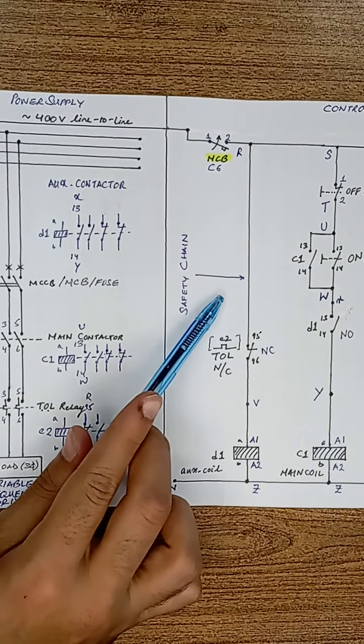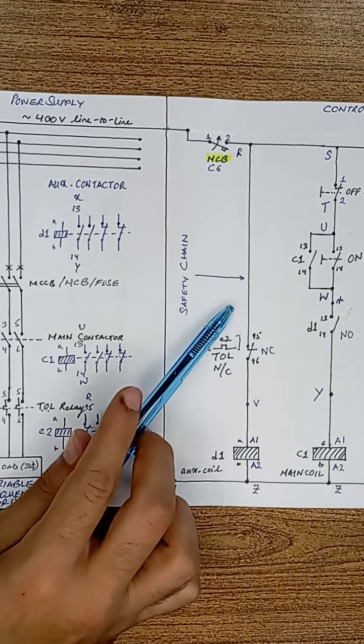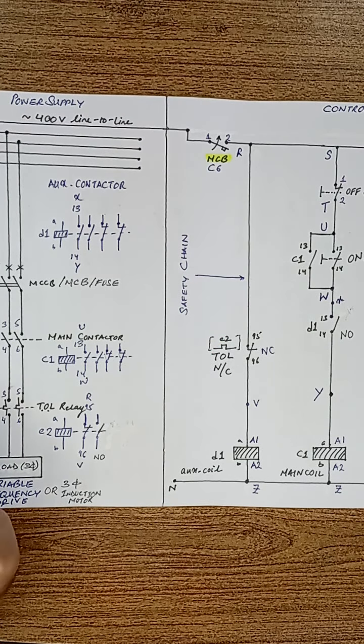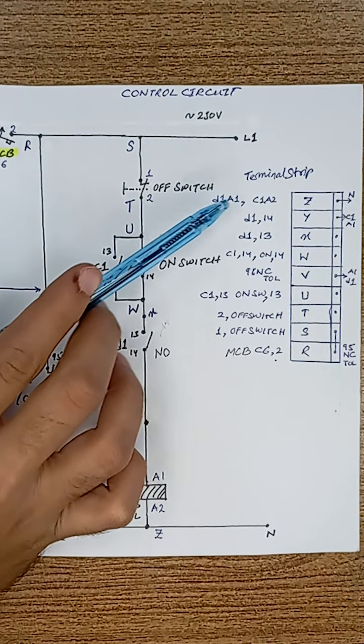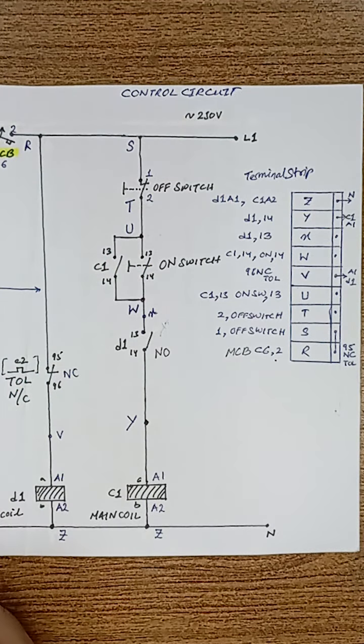In this line segment of our control drawing, we can add contacts from our safety relays such as thermal overload relay, PTC thermistor relay to trip the circuit in case of failure. And additionally, from this segment we can also form interconnections with other motors. This is the terminal strip. It is used to label connections, which makes it easier for us to physically put together this circuit and helps to avoid making wrong connections and rectifying the circuit in case of an issue.